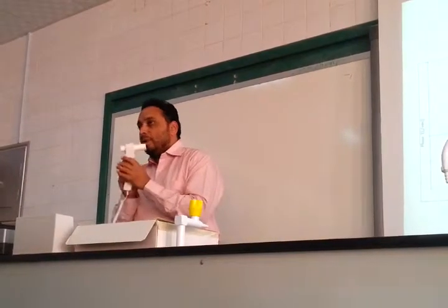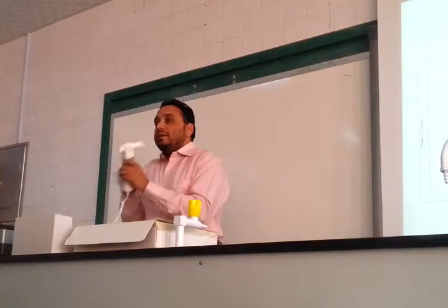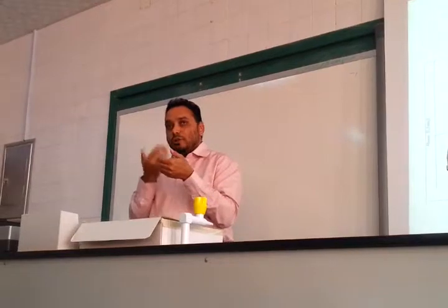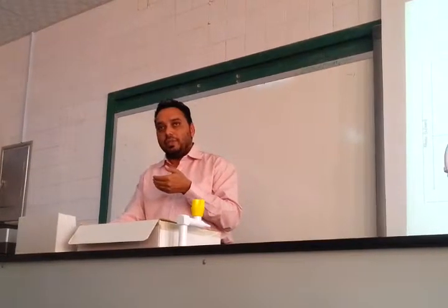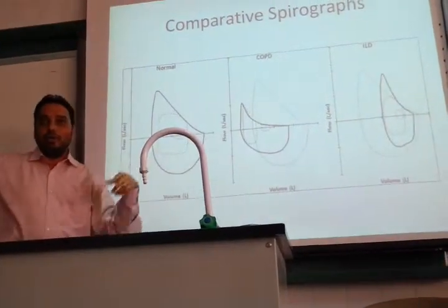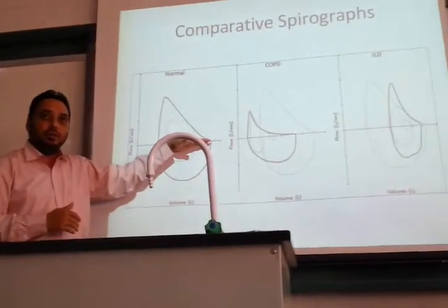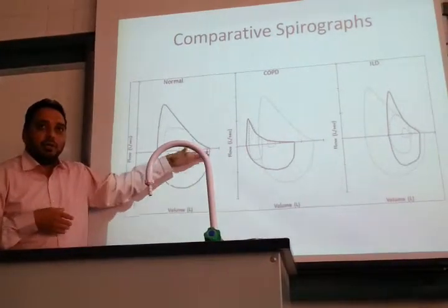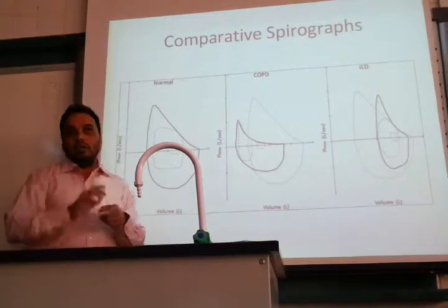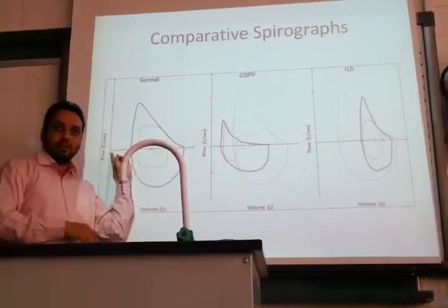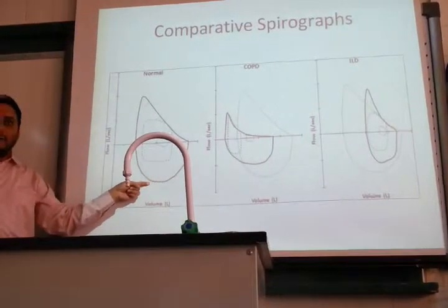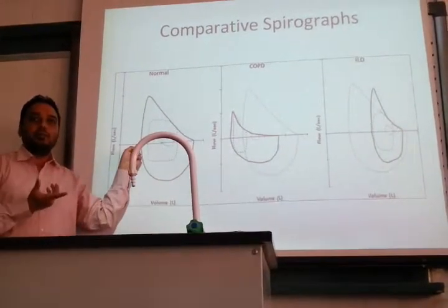After that, when you take in air, the membrane will move towards you, towards your mouth, isn't it? Inside the machine. That's why it gives a record. Electronically, the machine is recording that. So the movement of the membrane is towards the person. The membrane goes down, it records a negative deflection as compared to the baseline. As his inspiration is complete, it comes back to the baseline.